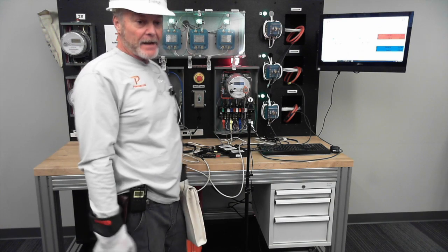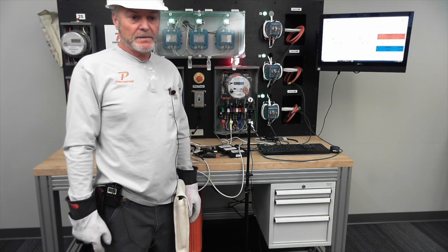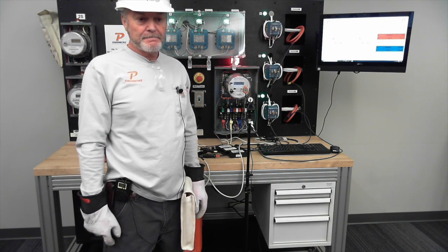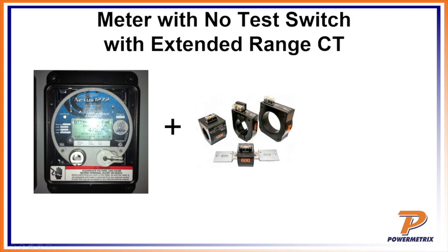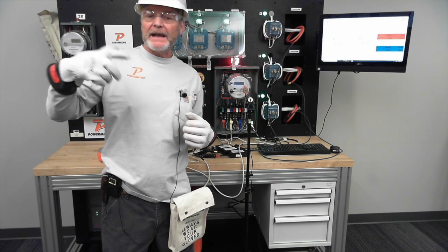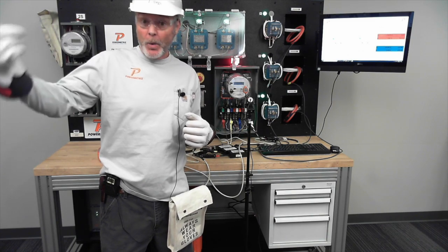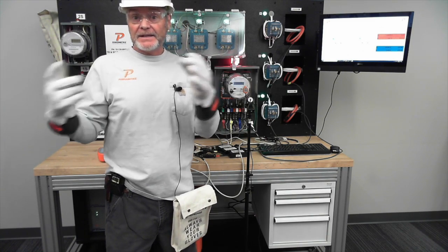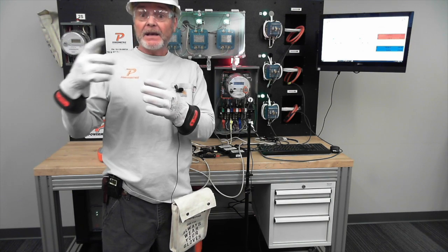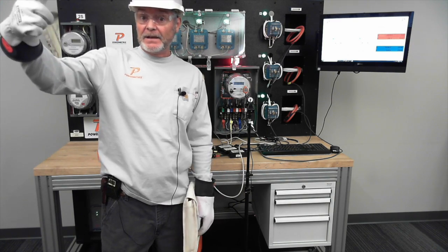All right. And then we wanted to show some other ones, right? So what happens if I've got no test switch, but I still have to clamp around, but also an extended range CT? With an extended range CT, I could have a little more current than 10 amps there, right? Yes, Chris is exactly right, because we've talked about this in previous webinars. With these rating factors of 3 and 4, what does that do to us on the secondary side of that transformer? Now I can go from 10 to 15 to 20, yes.